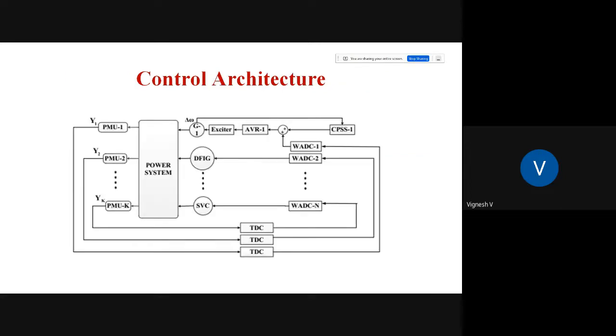The control architecture here is somewhat decentralized: we get data from the power system using PMUs, say Y1, Y2, up to YK. We pass this data through a time delay compensator, because the place where you measure the data could be geographically far from the place where the controller is. Then you have the wide area damping controller, which provides supplementary damping signals to, say, the SVC, DFIG, or even an existing AVR of the generator.